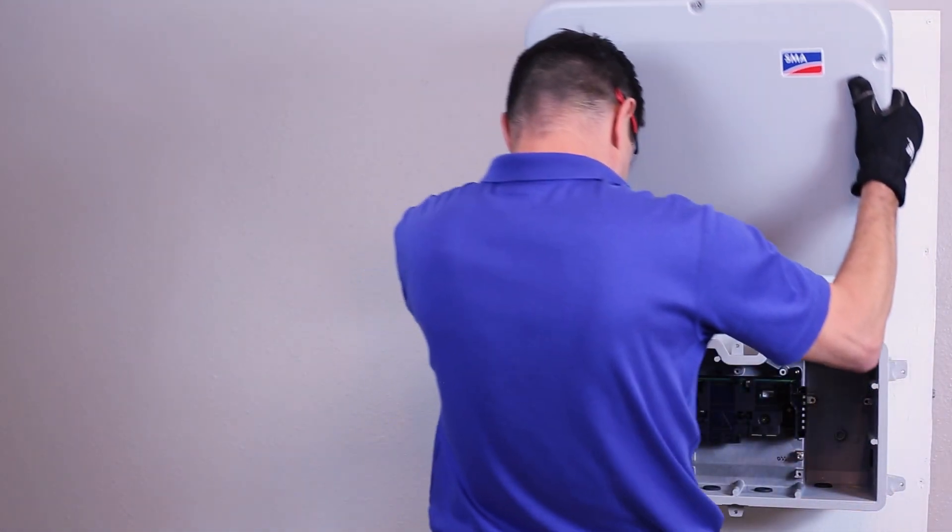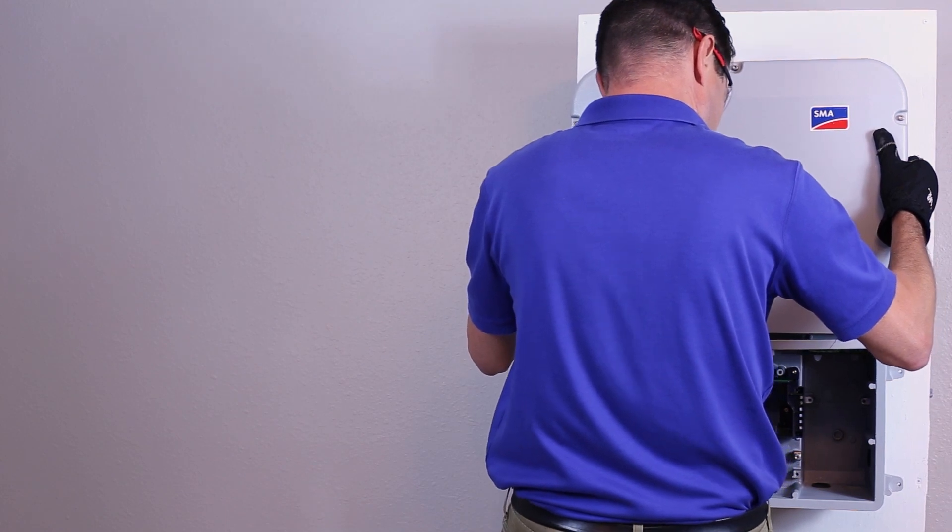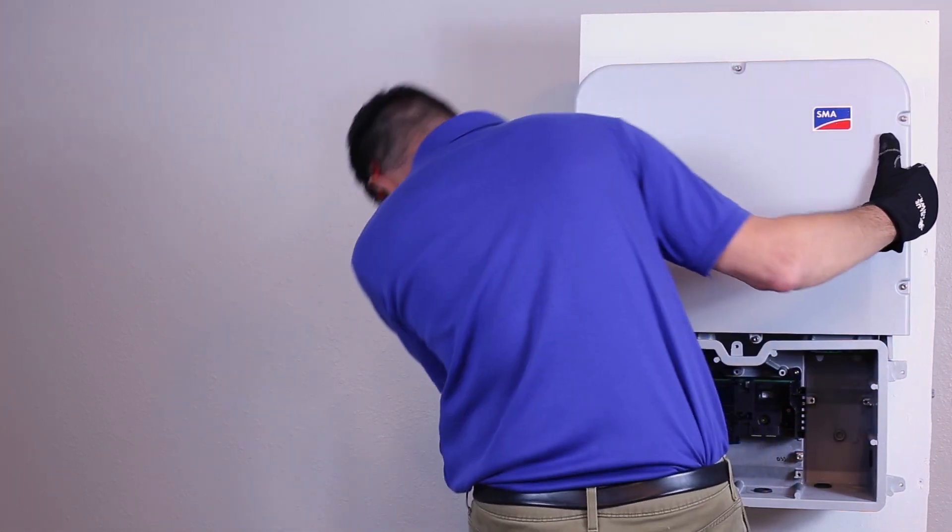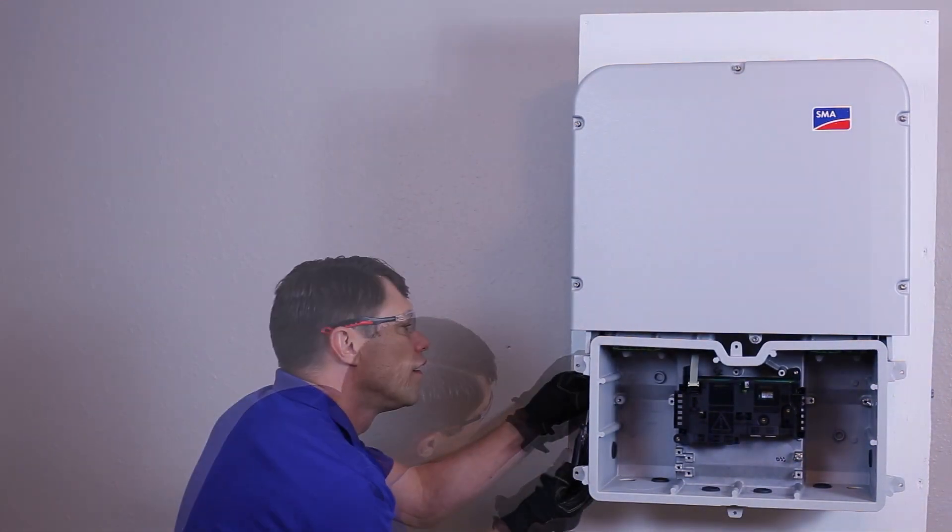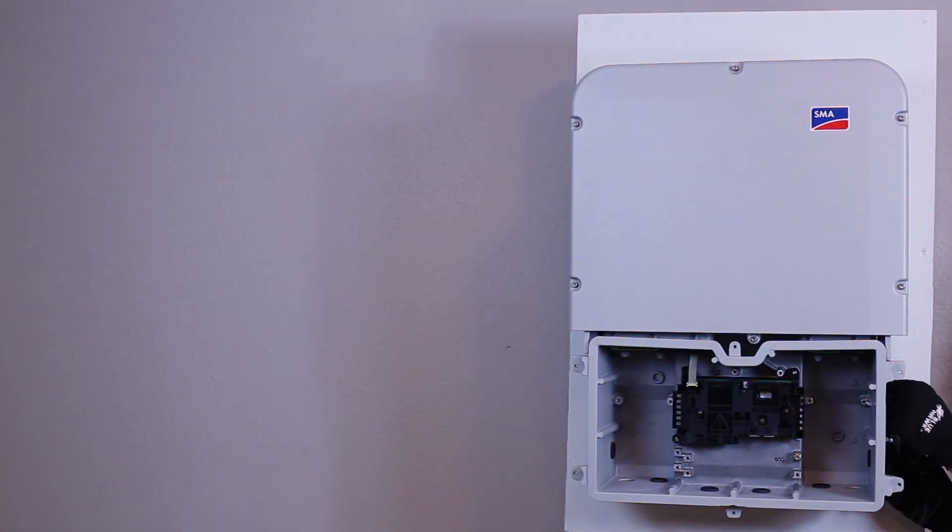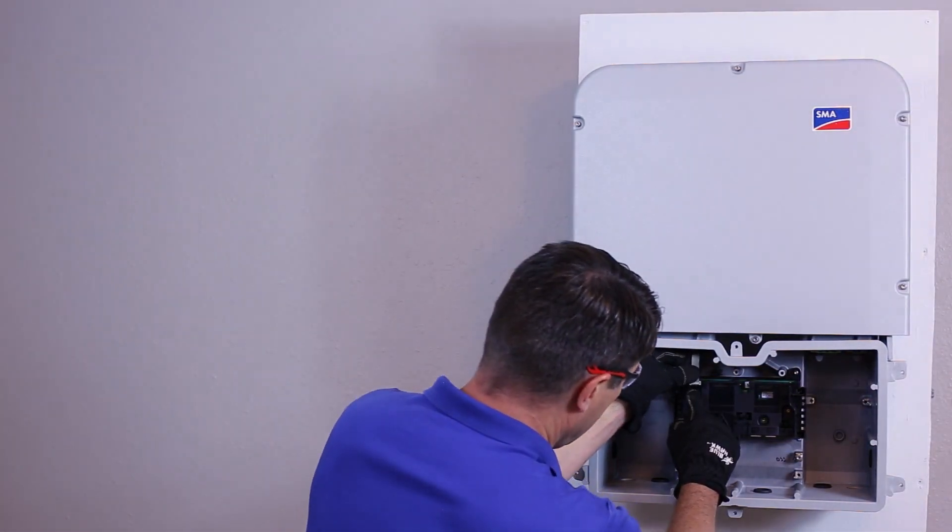Now the power unit can be placed on top of the connection unit and reattached. Ensure the ribbon cable is safely inserted into the connection unit and not pinched or damaged. Secure the power unit to the connection unit by reattaching the four Torx 25 screws and tightening to 53 inch pounds. Reattach the ribbon cable to the communications board.